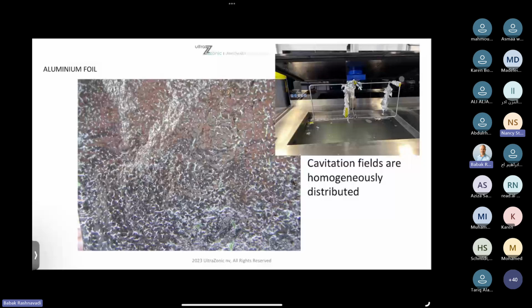Here you can see a frame with the aluminum foil in our ultrasonic device. We were just putting that in for maybe 20 seconds and you have this result. So here you can really see that the cavitation bubbles are doing their job. It doesn't mean that when the aluminum foil is totally destroyed, it will damage your instrument, because the instrument is stainless steel and aluminum is aluminum. It's just a foil. So this is really enjoyable to see, what kind of technology and efficacy we can prove.